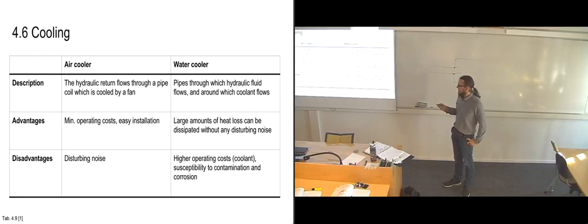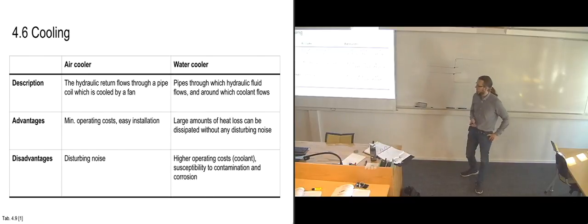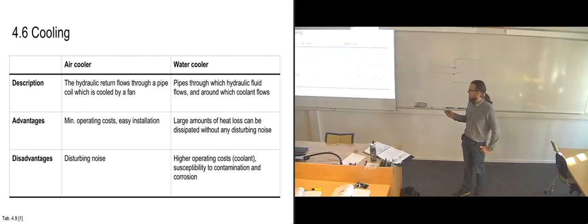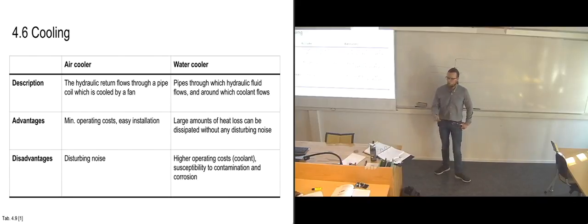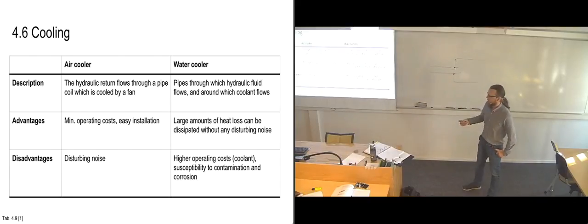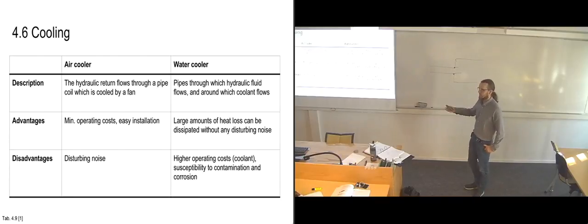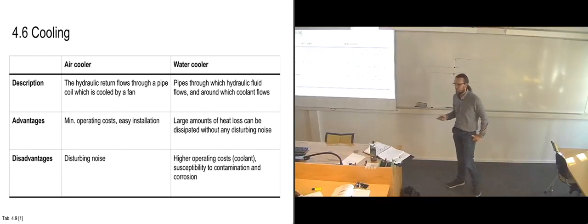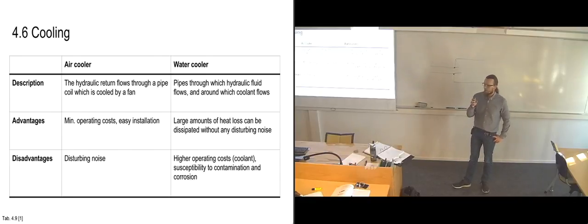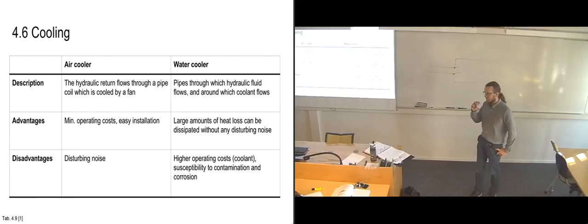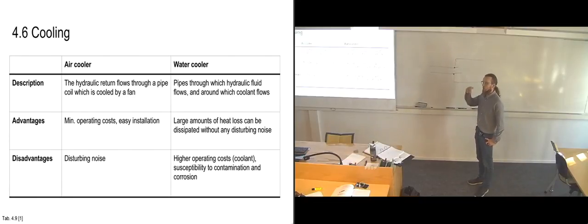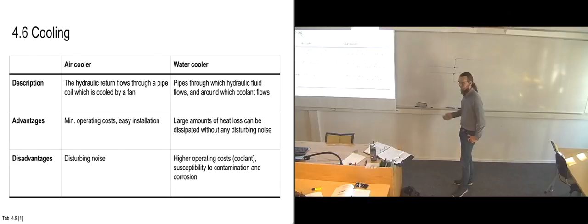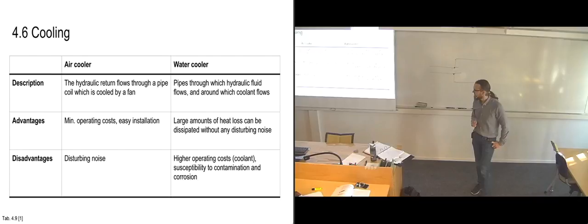And then you have the corrosion problem, of course, because you have submerged it in water. And also the problem with contamination, because since you have corrosion happening because of the water, you can also get corrosion ending up inside the pipes, so that you can get contamination inside it without really realizing it. So you can have corrosion creating a small hole in a pipe, where you will not only get oil into the water, but you will also get water into the oil, so that you get water in your hydraulic fluid, which isn't good.